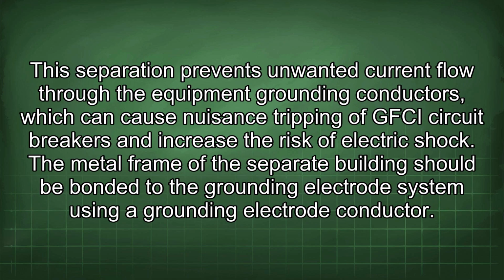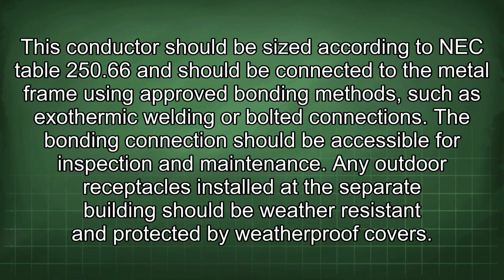This separation prevents unwanted current flow through the equipment grounding conductors, which can cause nuisance tripping of GFCI circuit breakers and increase the risk of electric shock. The metal frame of the separate building should be bonded to the grounding electrode system using a grounding electrode conductor. This conductor should be sized according to NEC Table 250.66 and should be connected to the metal frame using approved bonding methods such as exothermic welding or bolted connections. The bonding connection should be accessible for inspection and maintenance.